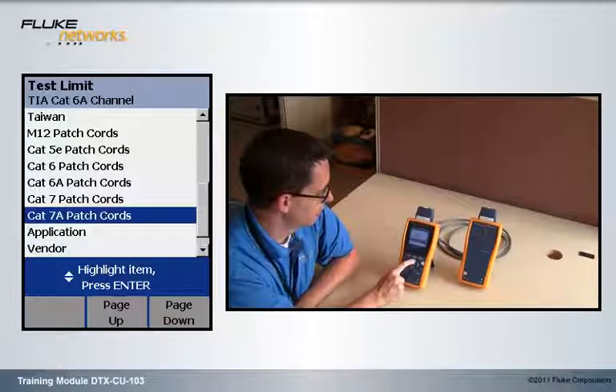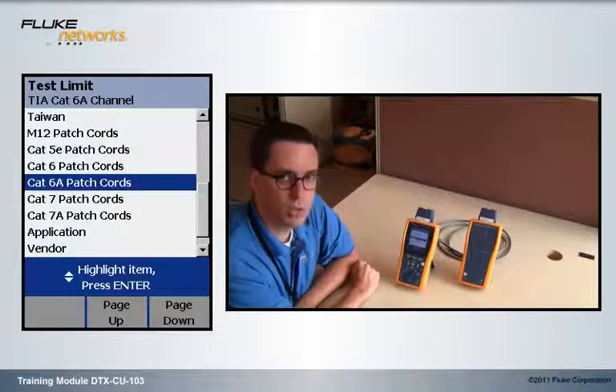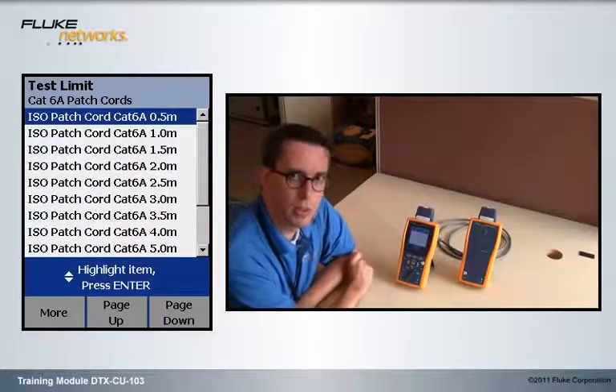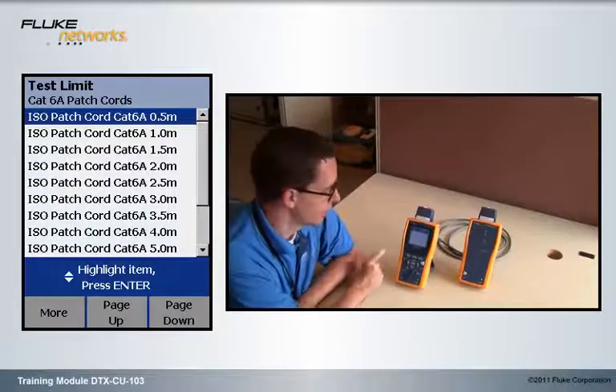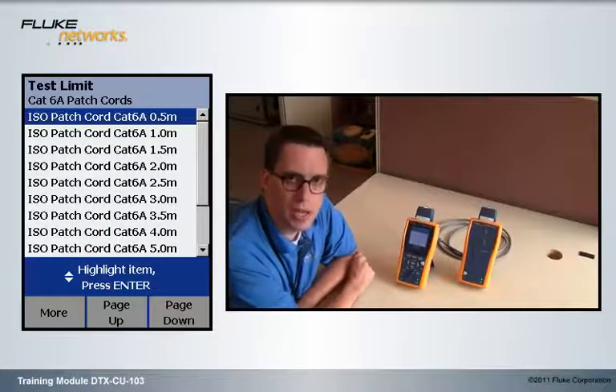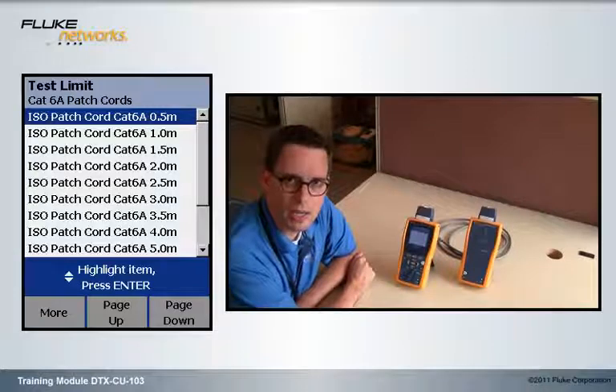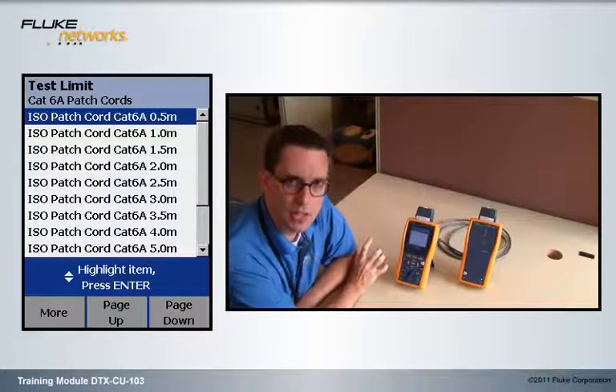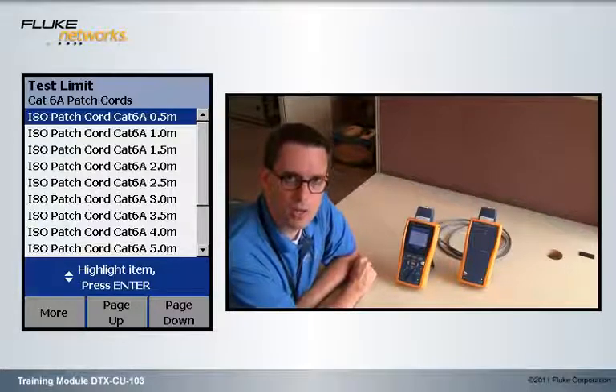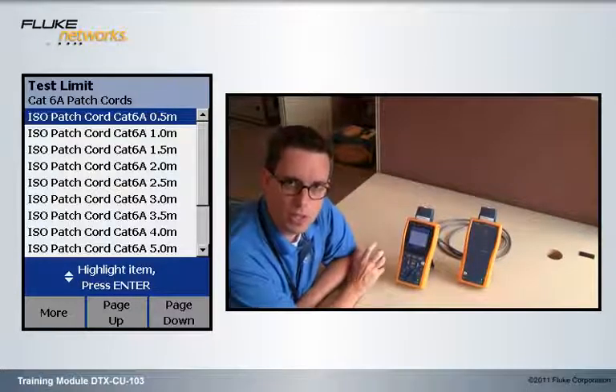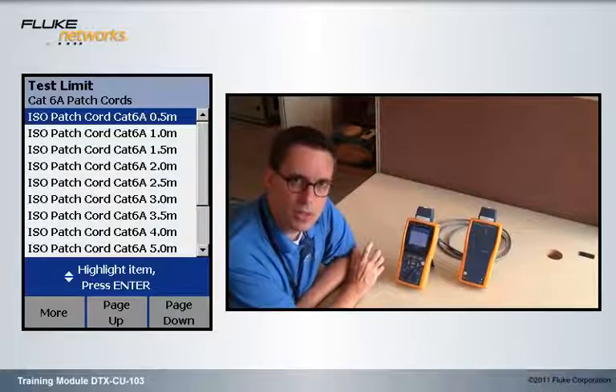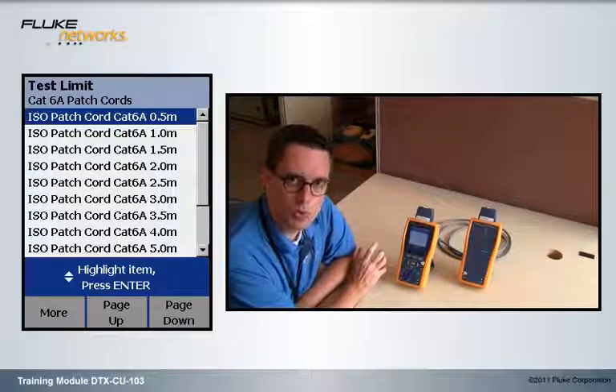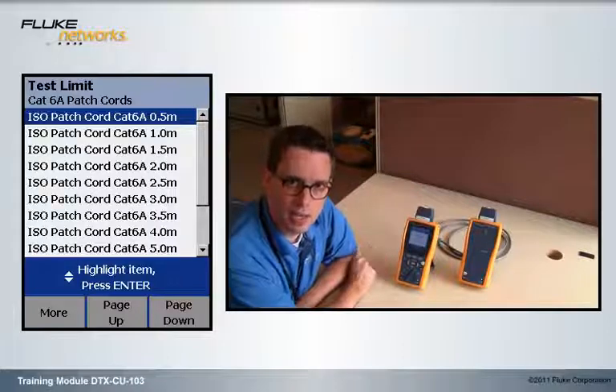So CAT6A patch cords, hit the Enter key. Now this is where we're going to pause for a moment. You're not going to get a TIA option for testing CAT6A patch cords. With 5E and 6, the TIA and ISO standards are aligned. With 6A, they're not. The ISO 6A connecting hardware is a little bit more strict than the TIA CAT6A connecting hardware.